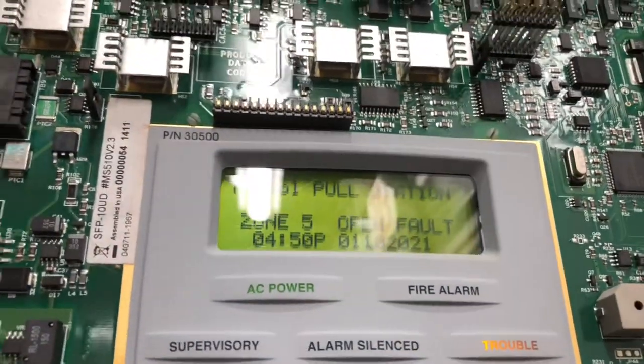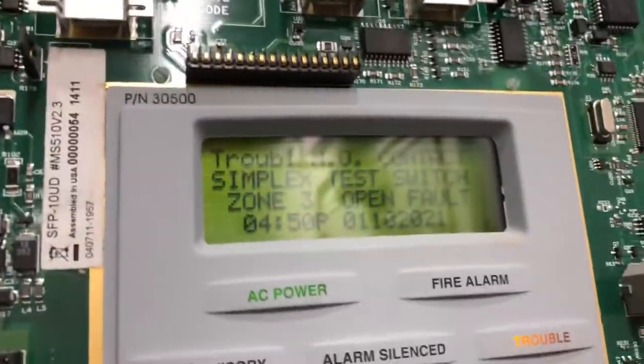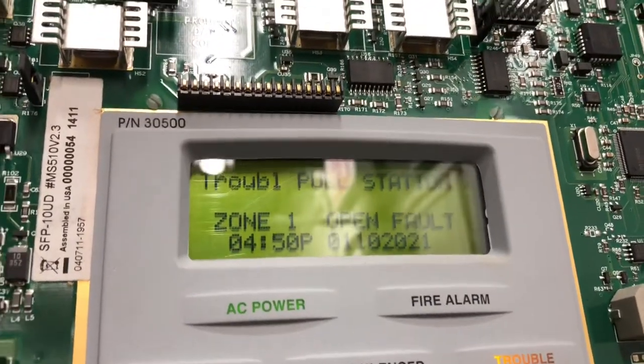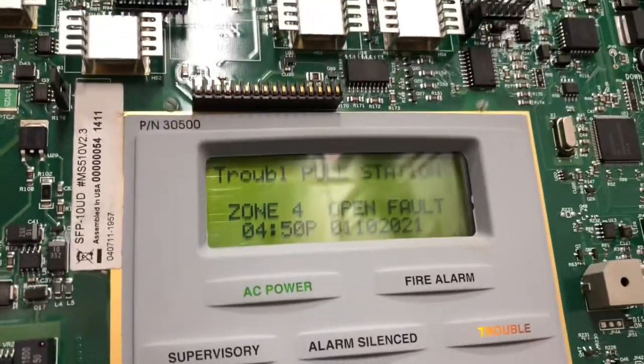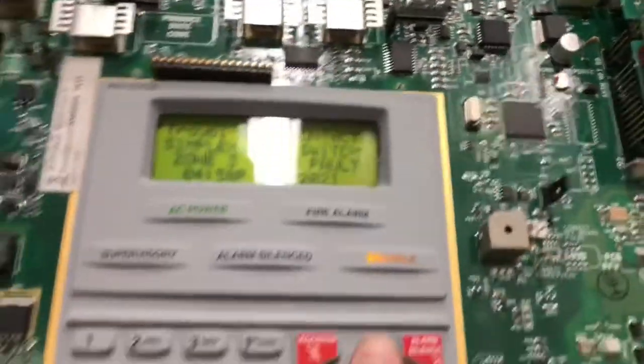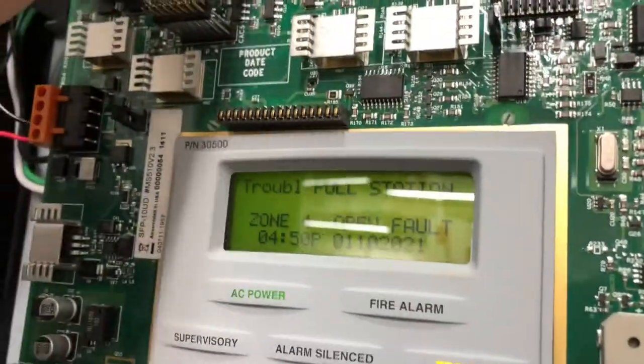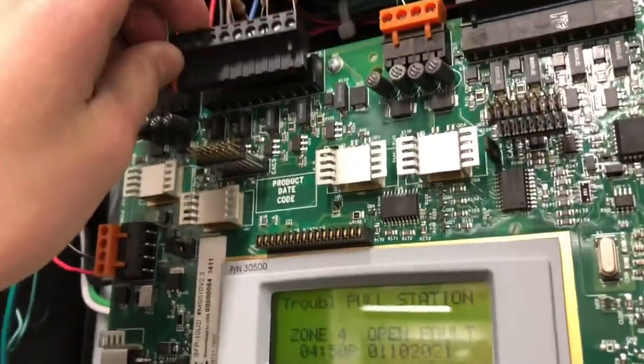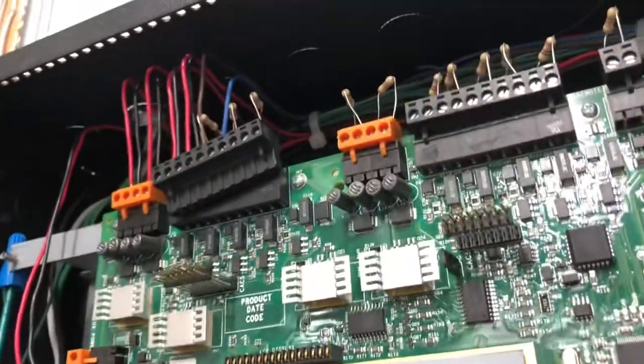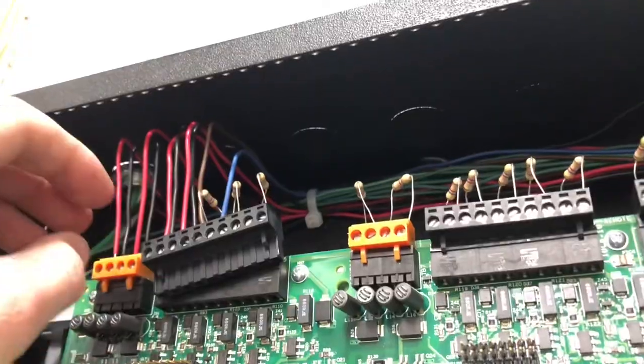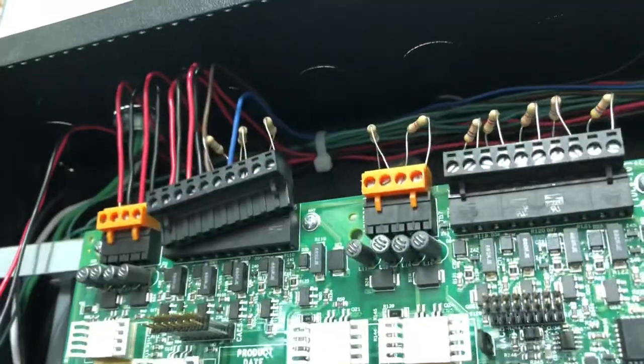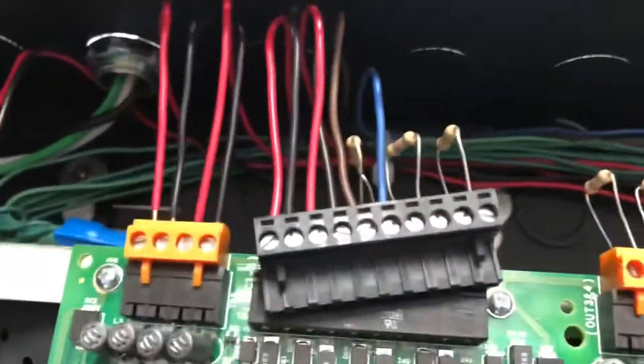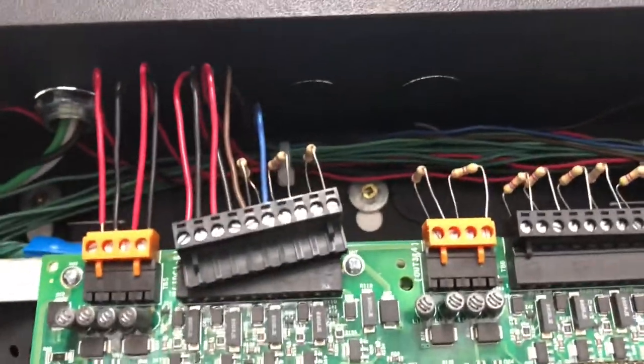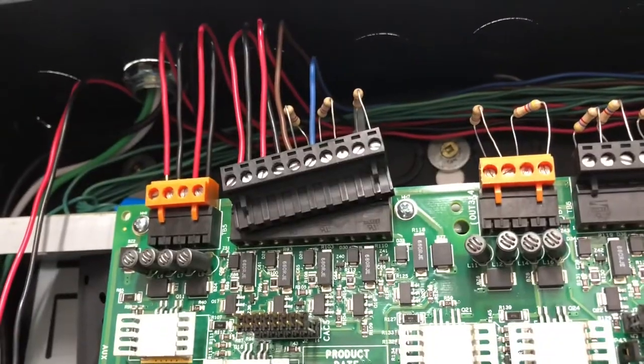So we got a few troubles. We have pull station open, zone 4, zone 5 is open, simplex test switch open, pull station zone 1, trouble zone 2. So we have a few different troubles at this point. One thing we don't have is a ground fault trouble, so we know it's on here. So now we're gonna test each zone individually. Now, depending on your terminal blocks, you might be able to pull each one individually, or you might be just unscrewing terminals to see. But either way, now you're gonna wanna get out a meter and figure out if it's a positive or a negative ground fault.